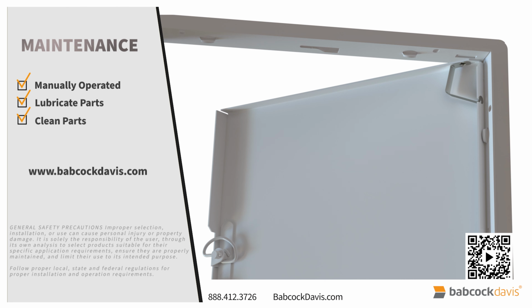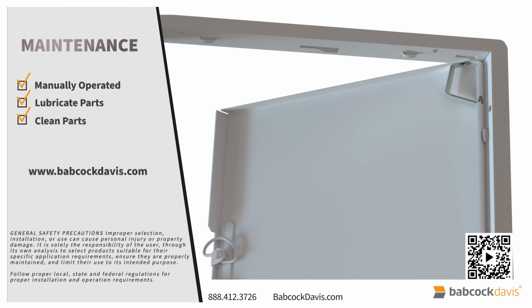Maintenance. Access doors should be manually operated once a year to check performance. Lubricate all moving parts such as hinges and latches with a silicone spray lube as required to maintain a smooth opening and closing of the door. Do not overgrease. Do not use regular lubricating oil as it can attract dust and grit. Non-moving parts can be cleaned with a mild soap or dishwashing detergent and water solution.